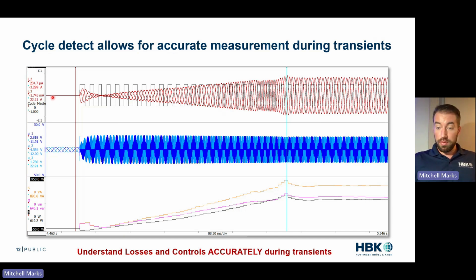So looking at an algorithm like cycle detect, it is quite effective in the transient. This is an example of a motor starting up. So we're in a vehicle, we're at 0 speed, we're out in the field, we start, the inverter kicks in, we see currents, and this black square wave is my cycle detect. This is my calculation period. And we're tracking that really, really closely as the motor's speeding up, as the amplitude's changing. You have confidence you're getting an accurate result. So we're averaging power, reactive power, apparent power on this time basis. And down in the bottom, we see what I call our power scope, where we can actually see the power cycle by cycle while this motor is accelerating. We can actually follow our motor control. We can see where we have overshoots. We can really understand in great detail how this machine is operating and then understand, can I tune this point here to lower my losses? So understanding losses and controls accurately during transients is a real benefit of using an appropriate measurement period.